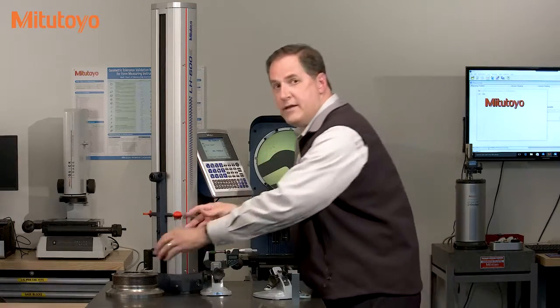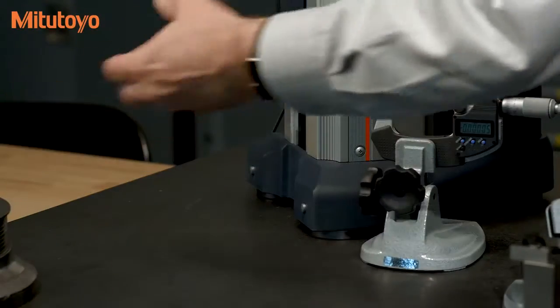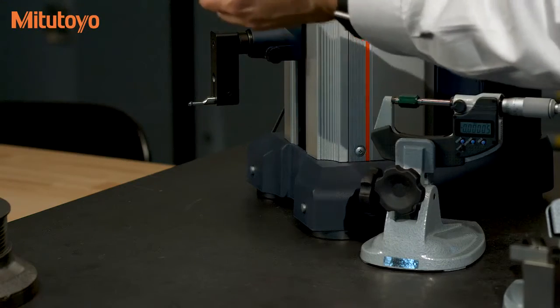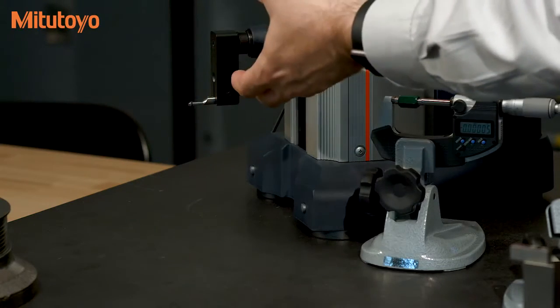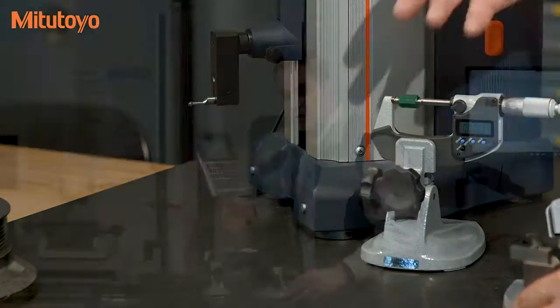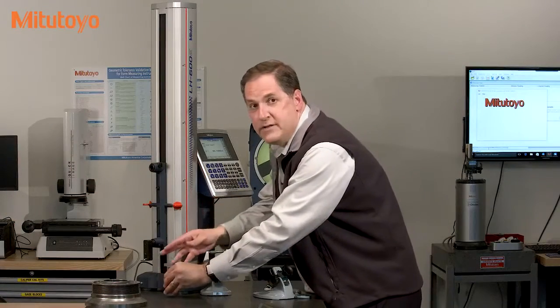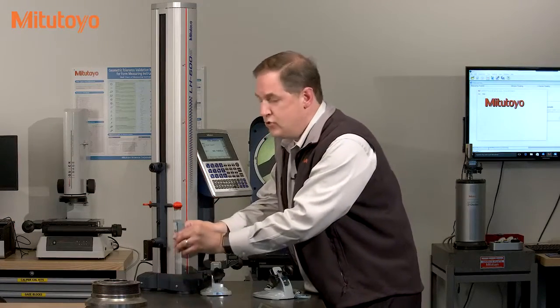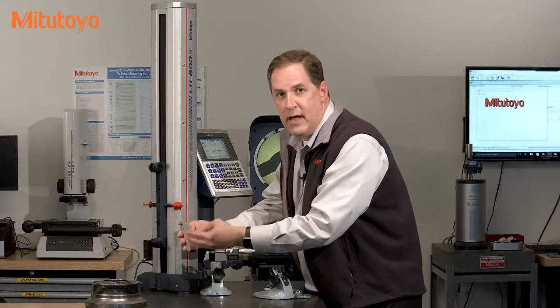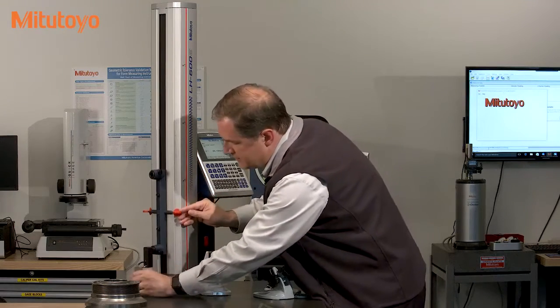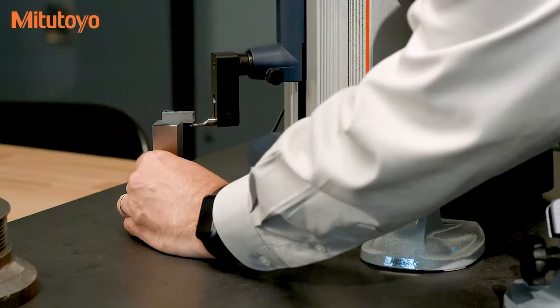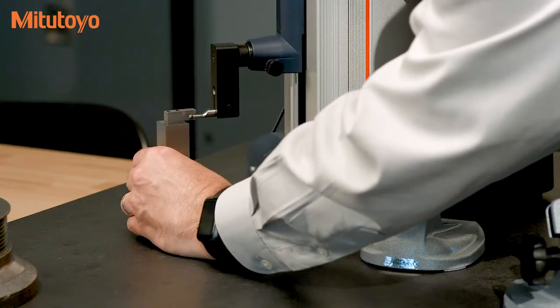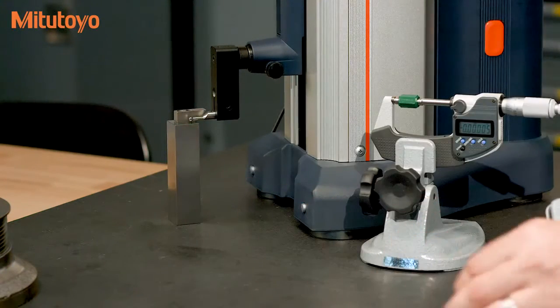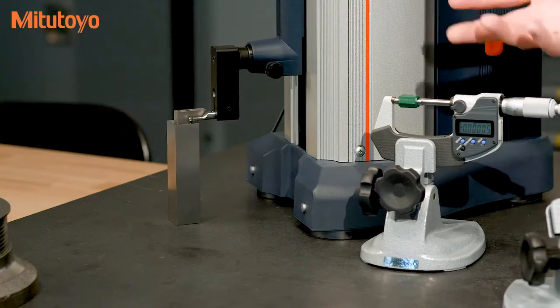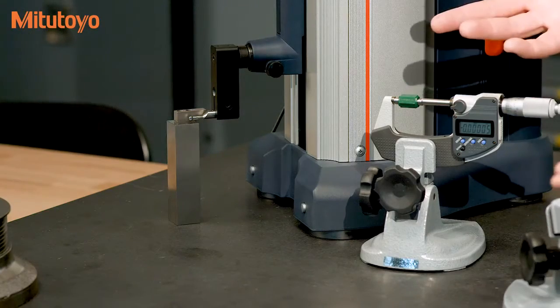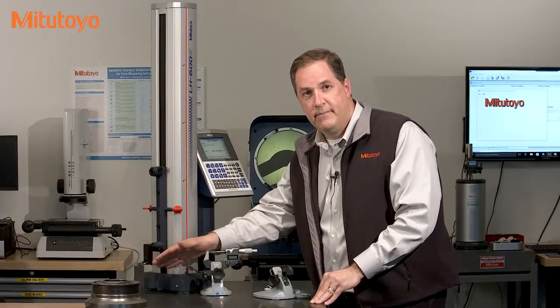On the linear height here, we have interchangeable probes. When each of the different probes is used, or at some other time during the use of it, the probe needs to be calibrated. This is usually done with the probe calibration block. By measuring this in different directions, we're able to determine or calibrate the probe diameter.